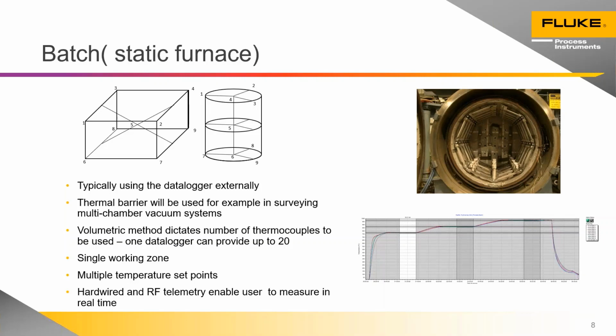Before we dive into the software, there are two or three slides now just on thermocouple positioning, on the topic of working volumes and thermocouples to be used. The TUS is a process designed to show there's uniformity through the working volume of the furnace and that it meets the requirements of AMS 2750.